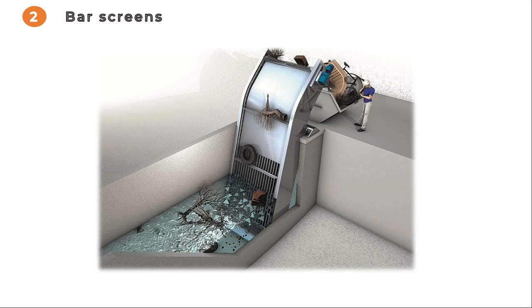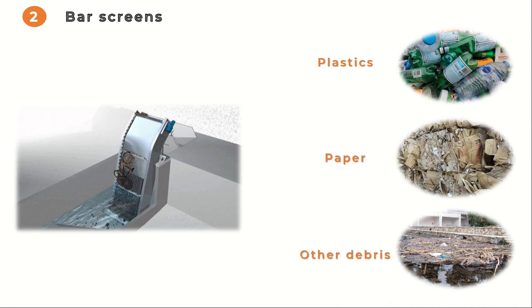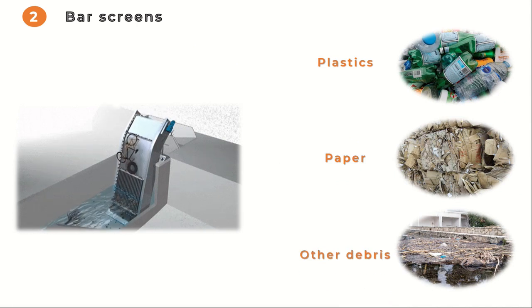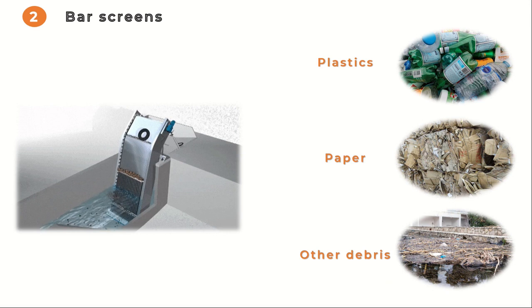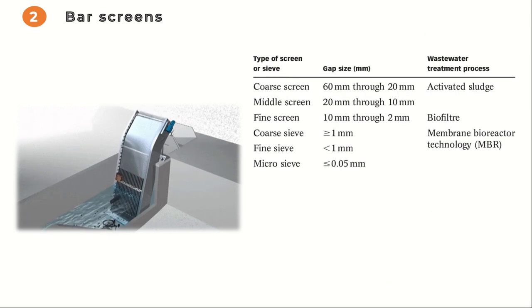The second step in the process is the use of bar screens. Wastewater passes through screens that are designed to remove large items such as plastics, paper, and other debris. This prevents these items from entering the treatment process and causing blockages or damage to the equipment. Wastewater treatment screens can be broadly classified into three categories: coarse, fine, and micro.